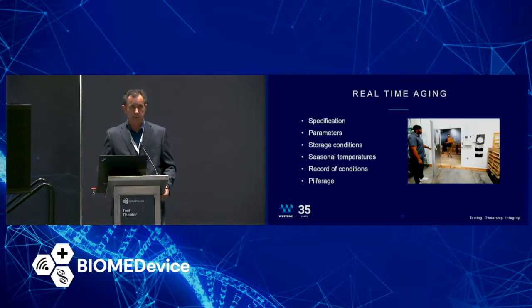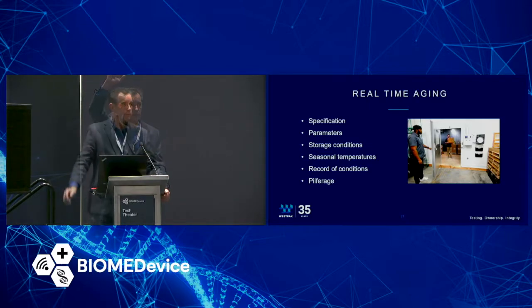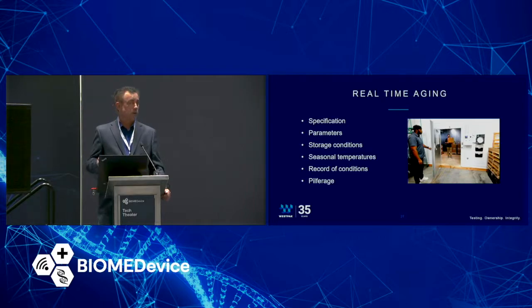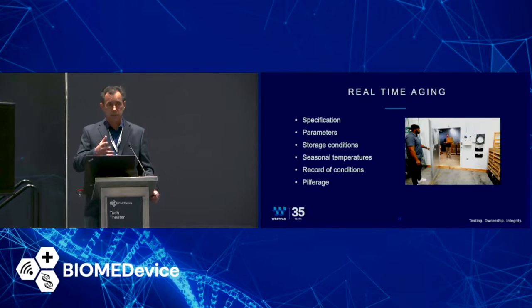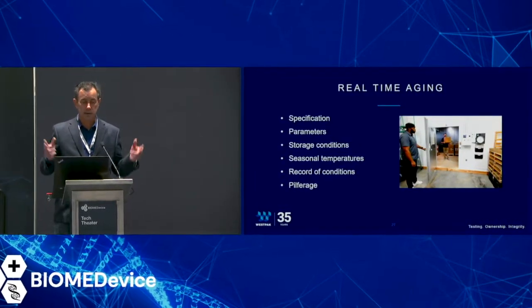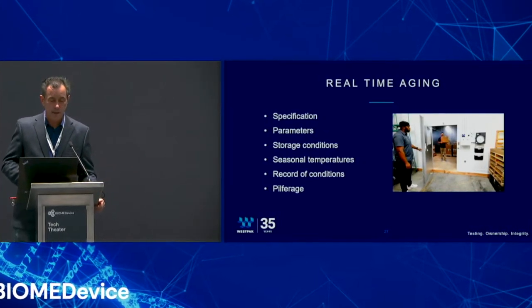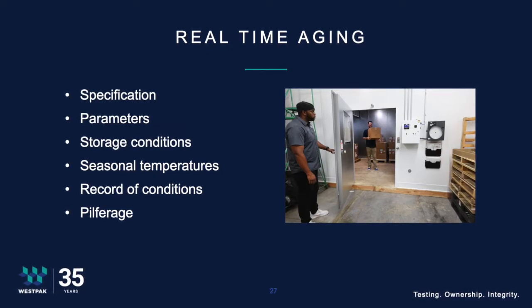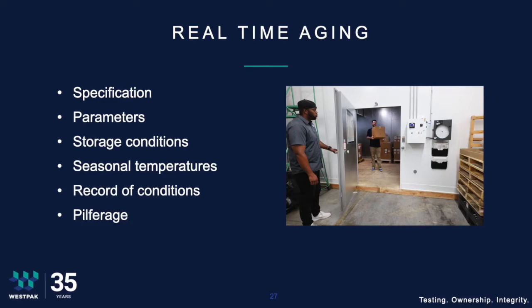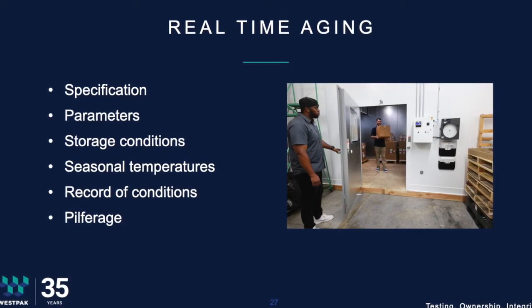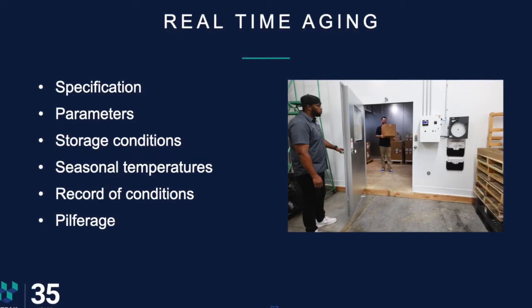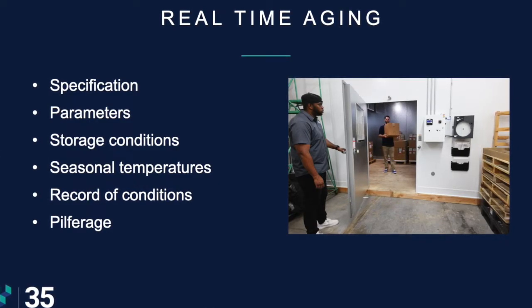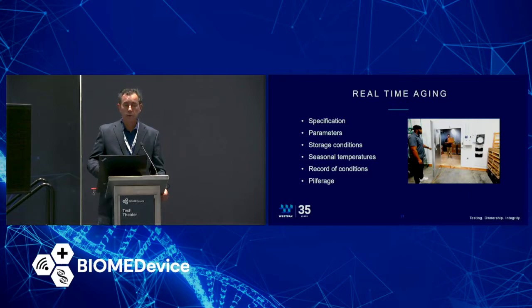Now let's talk about real-time aging. Does anybody know of a real-time aging standard? No, because there isn't one — there's no standard, no specification for real-time aging. So how are we going to define the parameters and storage conditions? We can look to ASTM D4332 for standard conditions, but they don't really call them storage conditions, and everybody's storage conditions will be a little different depending on where you are. You also need to consider seasonal temperatures and recording conditions. If you put samples in a cubicle, do you have a record of those conditions, and what about pilferage?